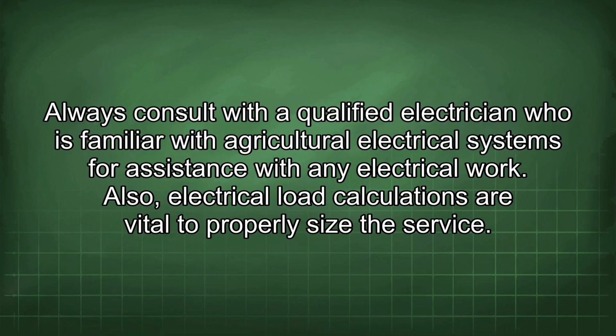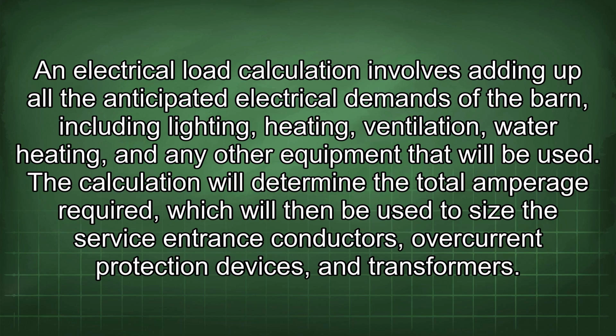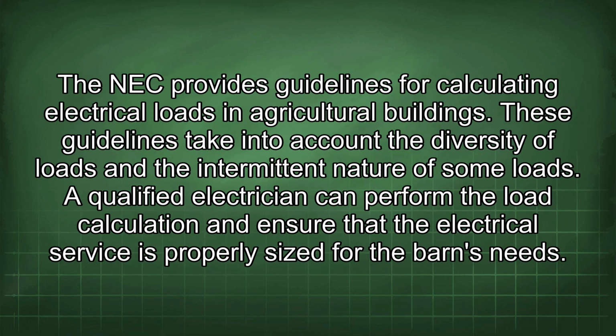Also, electrical load calculations are vital to properly size the service. An electrical load calculation involves adding up all the anticipated electrical demands of the barn, including lighting, heating, ventilation, water heating, and any other equipment that will be used. The calculation will determine the total amperage required, which will then be used to size the service entrance conductors, overcurrent protection devices, and transformers. The NEC provides guidelines for calculating electrical loads in agricultural buildings. These guidelines take into account the diversity of loads and the intermittent nature of some loads.